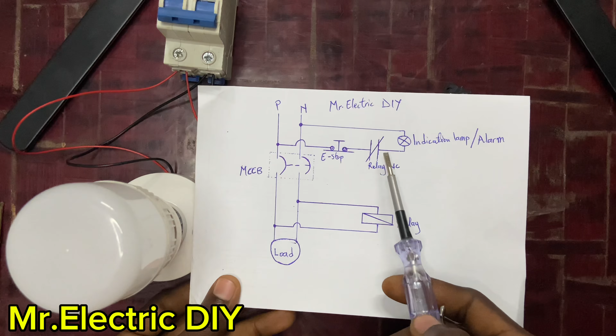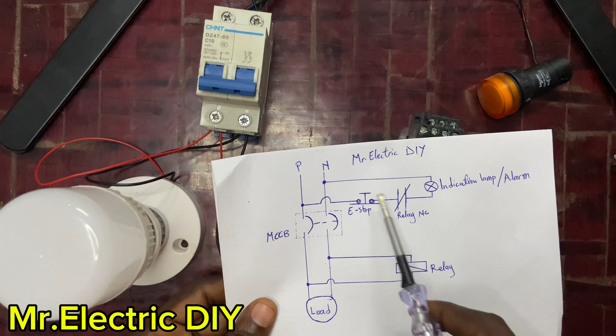Now we have successfully connected the load and the relay. So what I have to do is to connect my indication lamp or the alarm. And as I said, I'm using this lamp. This yellow indication lamp over here. So what I have to do is, I'll connect the neutral from this side to the lamp. The neutral from the top side of the breaker to one side of the indication lamp. I'm done with this section. It's left with the emergency stop and the normally closed contacts on the relay.